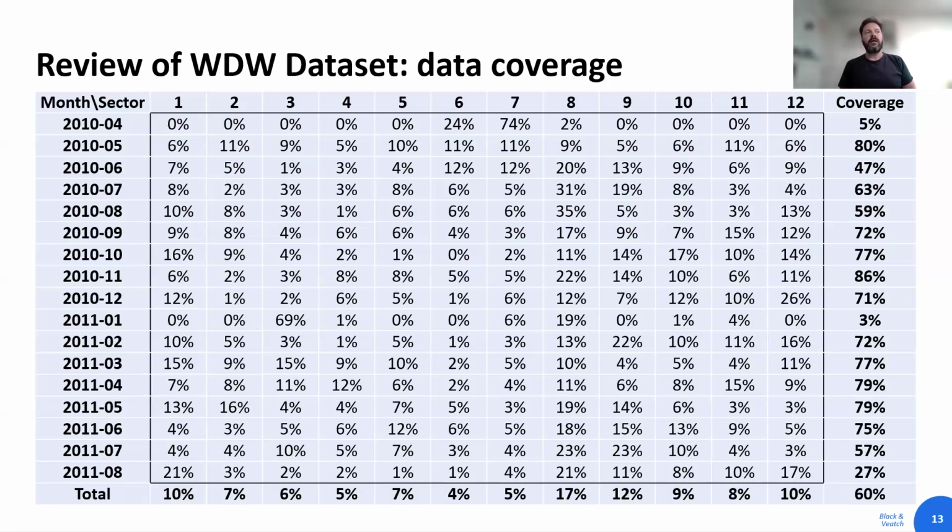As you think about something like a month for one turbine, taking data for something like the prevailing wind sector, you could potentially vary the size of the direction sector you're considering to try and get enough data that you'd get a reasonably robust calculation of your performance metric. I would say I probably wouldn't want to go much lower than a month.